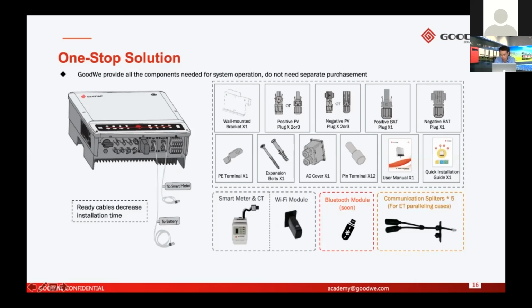Okay, and this one is for the SEC 1000. The connector is for ET paralleling. For ET parallel, you have to daisy chain all the communication cables of all the inverters, then connect them to the SEC 1000. So you have to use a Y connector, a splitter, to daisy chain all the inverters, all 18 inverters.